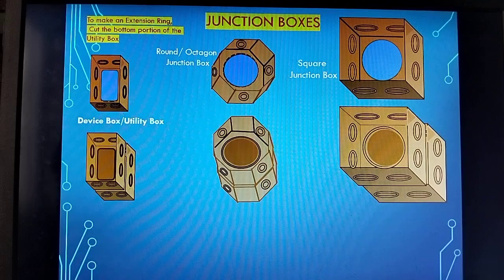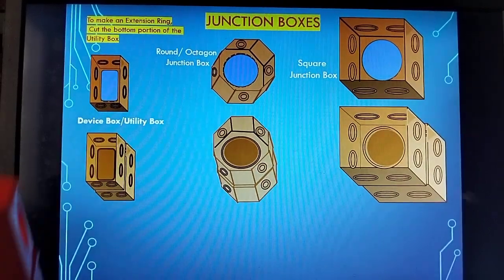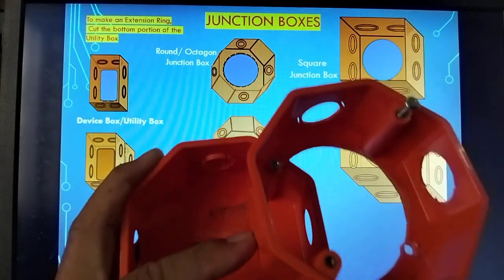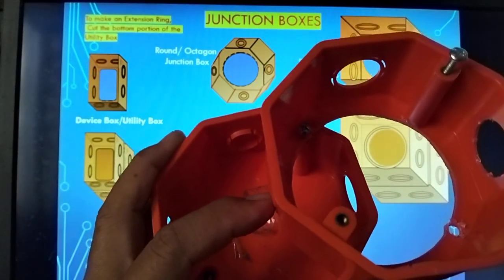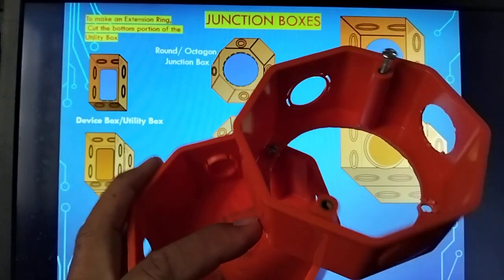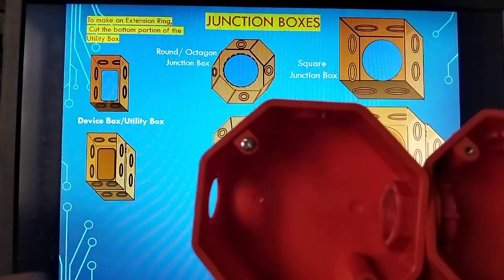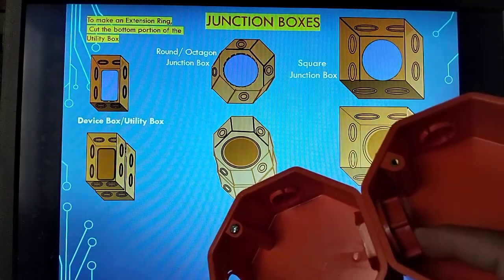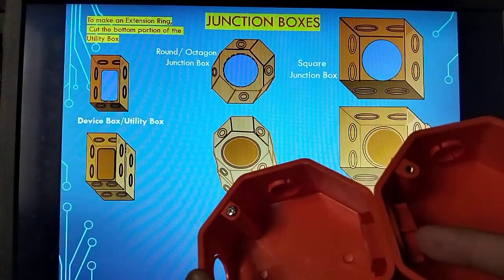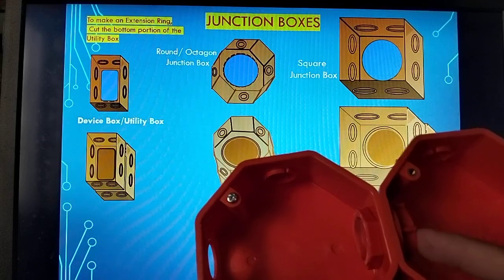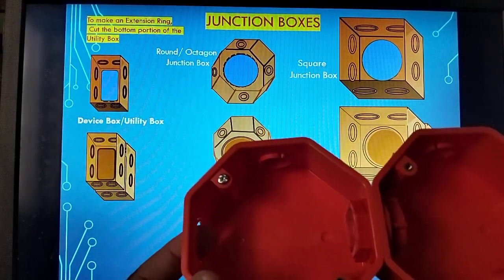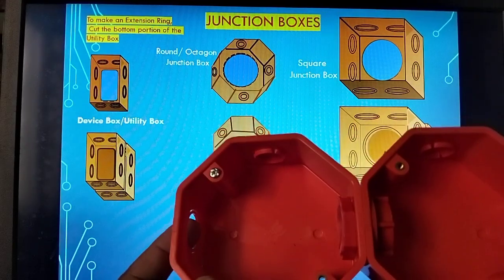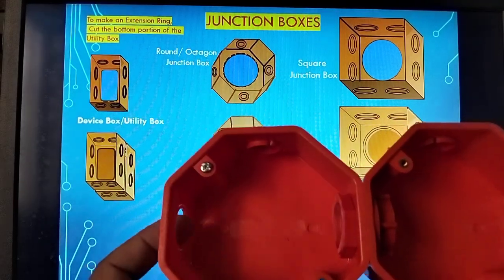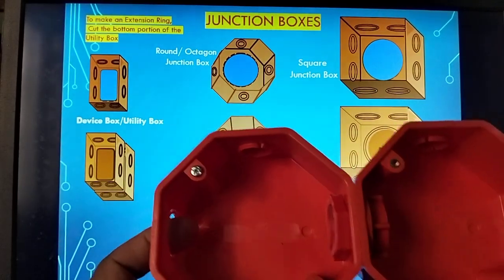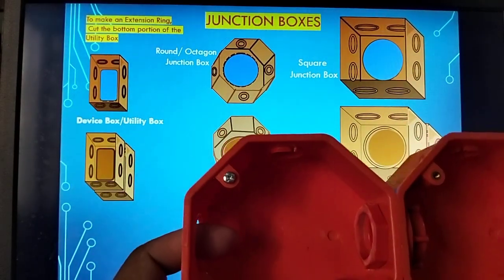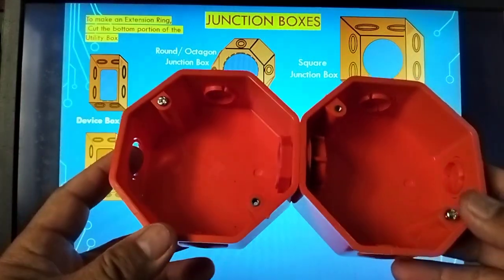Let's say you don't have a hole saw, problem, no? You don't have a hole saw, you cannot fabricate like this, then use another junction box the same, use this pipe connector or bushing, put side by side, connect side by side to increase the capacity of the junction box in the same area. Let's say it is inside the ceiling or concealed, so you increase the capacity of the junction box.